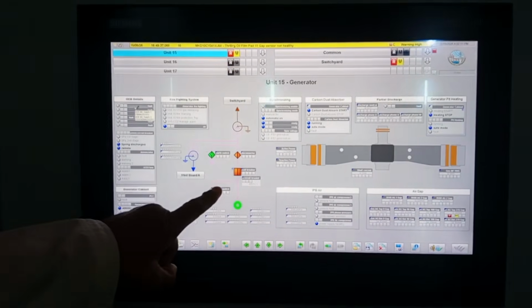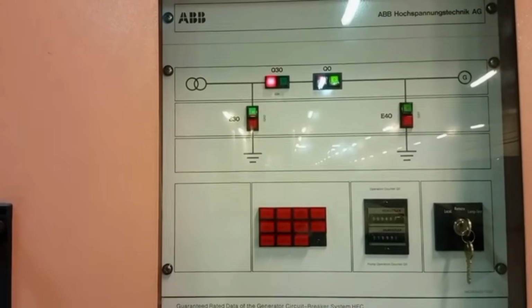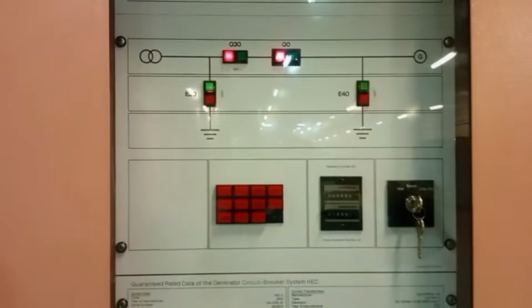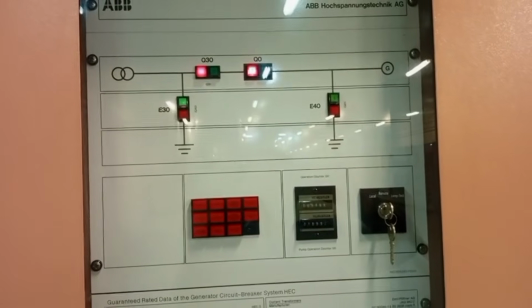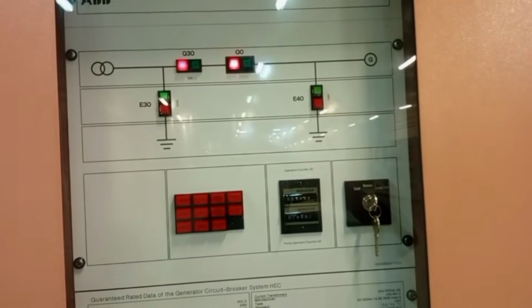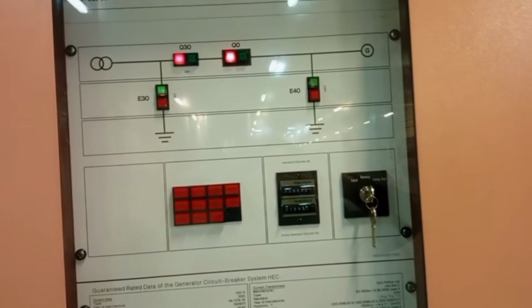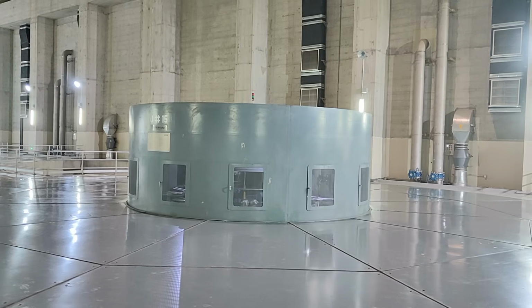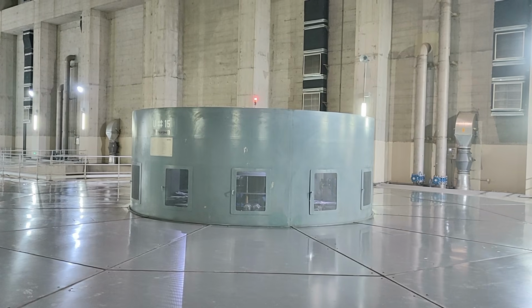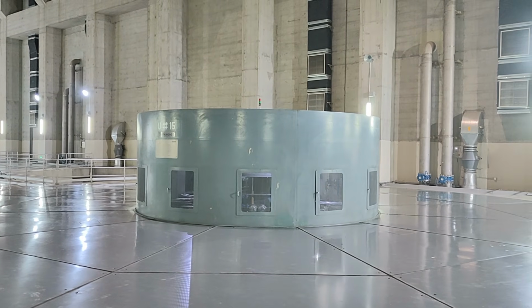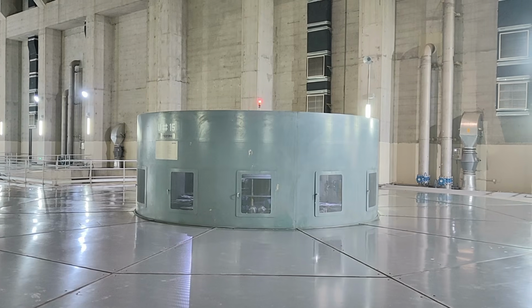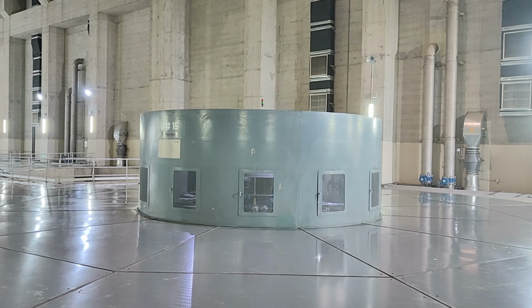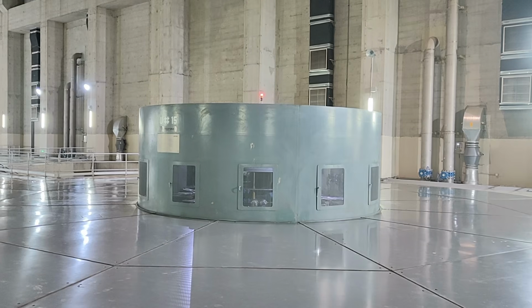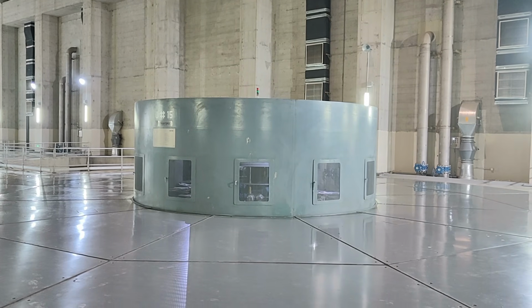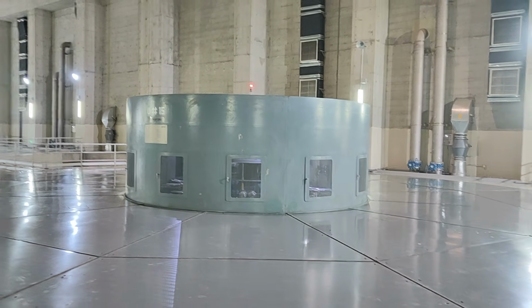And when both waveforms align perfectly, the generator circuit breaker closes. That single click locks the machine into the national grid. Once synchronized, excitation no longer controls megawatt. Water flow controls megawatt. Excitation controls reactive power, MVAr.